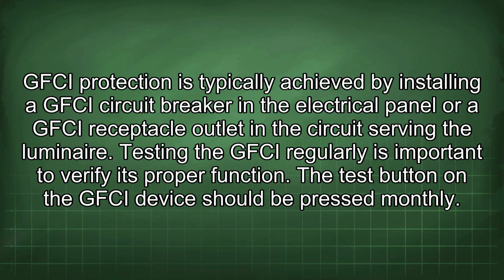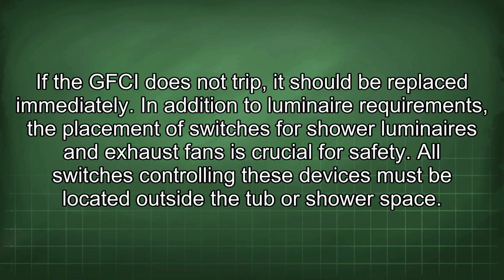GFCI protection is typically achieved by installing a GFCI circuit breaker in the electrical panel or a GFCI receptacle outlet in the circuit serving the luminaire. Testing the GFCI regularly is important to verify its proper function. The test button on the GFCI device should be pressed monthly. If the GFCI does not trip, it should be replaced immediately.